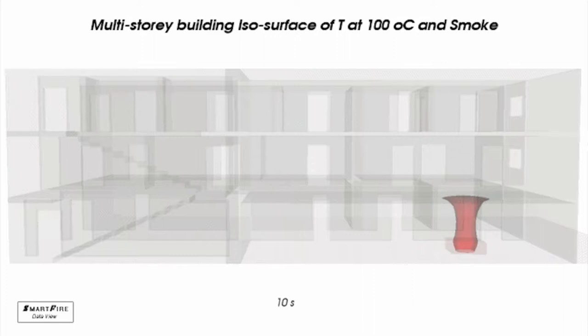Not only that, but because we're knocking down the temperature in the fire compartment, we're taking the energy out of that plume. So instead of the plume pouring out and rapidly filling upstairs, we have a much lazier plume that's not going to spread so effectively. This gives us a lot of protection to the escape route, remote from the actual fire room of origin.